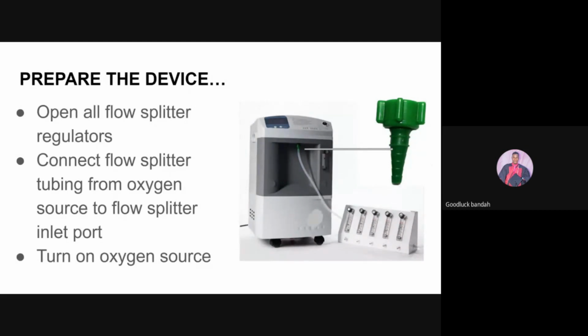Once you have done that, it's time to connect your flow splitter to the oxygen source. In our case, we have an oxygen concentrator, which is giving oxygen to the flow splitter. You have to make sure that the tubing connecting the flow splitter and the oxygen supply is tightly fixed to the Christmas tree shown on the left on the slide. The Christmas tree connector is the one shown in green color. Make sure that it is tightly connected with the tubing, and that the tubing is also tightly connected to the oxygen splitter. Once you have done that, you have to turn on the oxygen source.